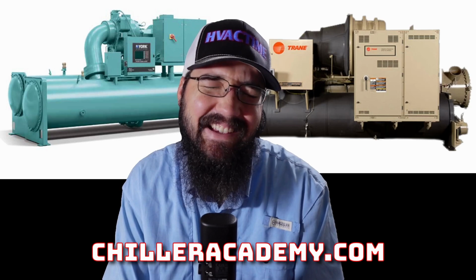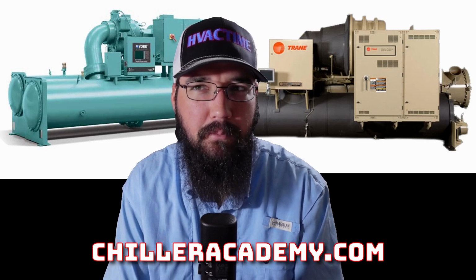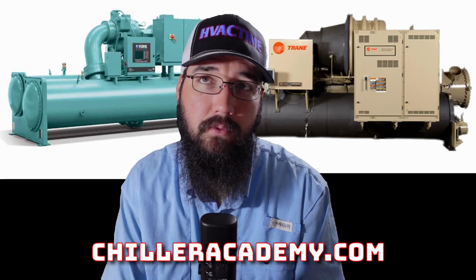Now, technically, on a super specific level, the high pressure refrigerants, I believe, are considered more like medium pressure on a refrigerant scale. So we're not dealing with the thousands of PSIs. So I think, if I understand right, on a standard scale, it's considered medium pressure. But from a chiller perspective, we have high pressure and low pressure. That is the designation that will separate these. This will be how it's referred to in the manufacturer's literature.